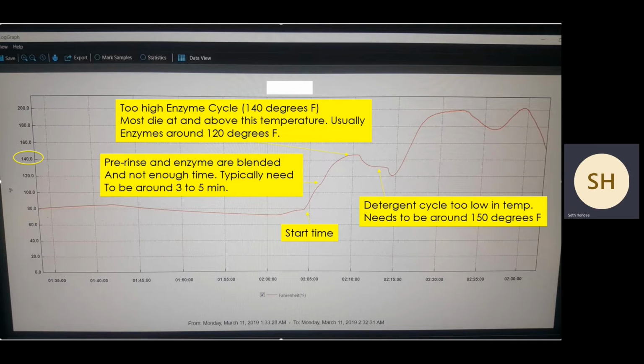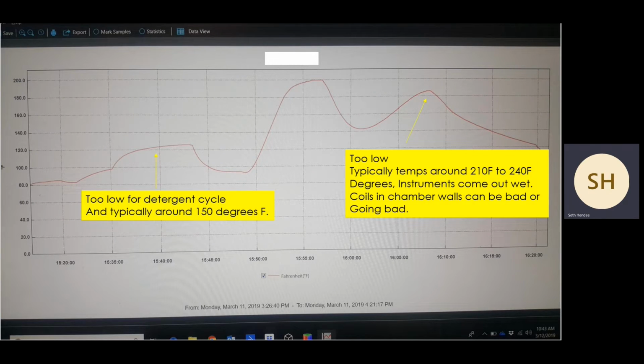Then sadly, we have a dip at a point where we expect it to go up. Detergent cycle temp is too low, right? That needs to be around 150. And if you're using an enzyme and then a detergent, you'll normally see the detergent itself doesn't have enzymes in it, so you don't have to worry about the enzymes being a problem because the enzyme part happened first, and then the regular detergent cleaning that doesn't have enzymes is in the next phase, and it can be higher. Now, this is the second part of the plot, right? This finishes out the cycle. And we see here that it's too low.